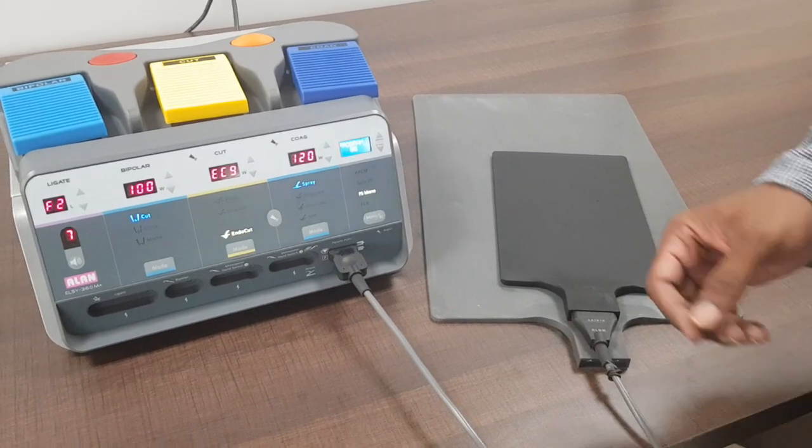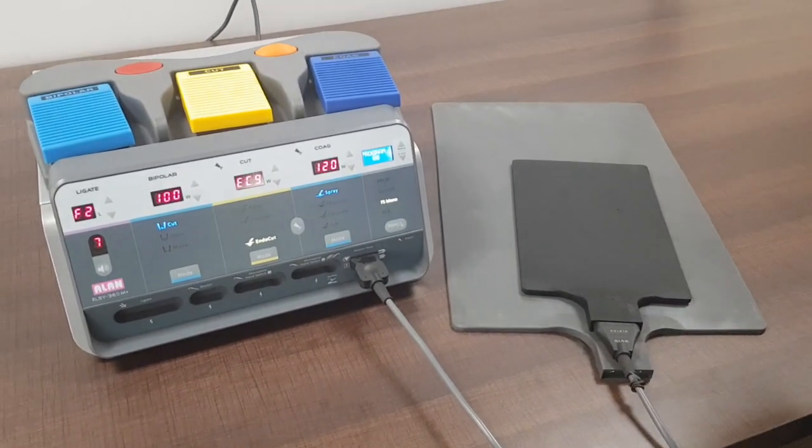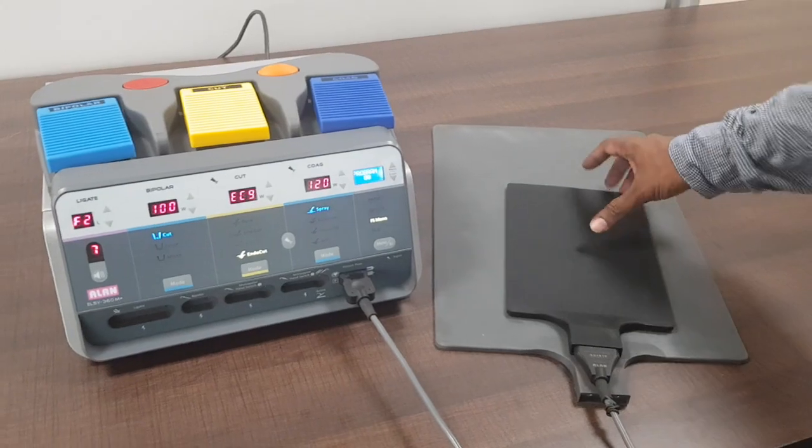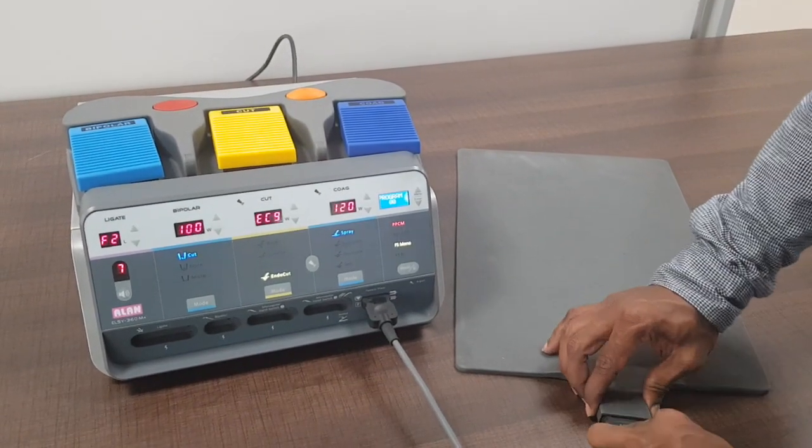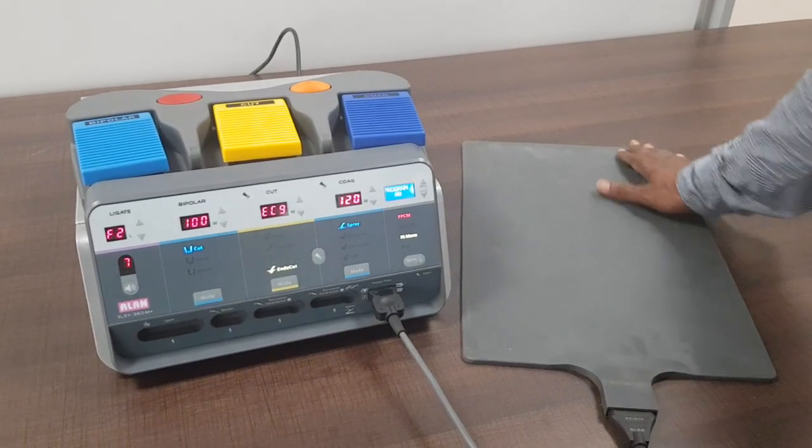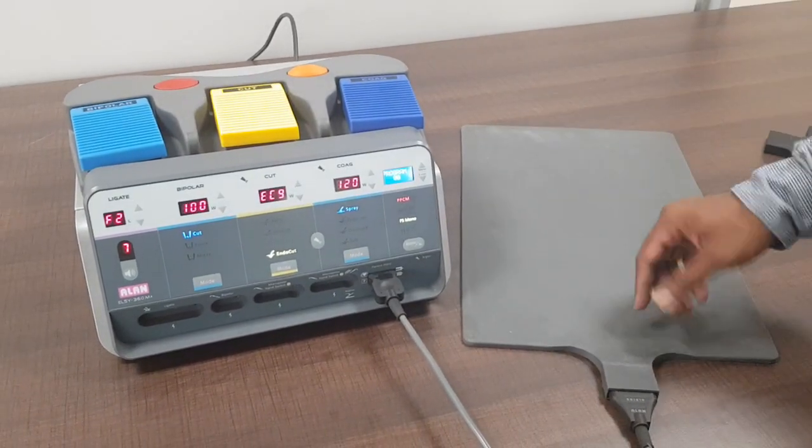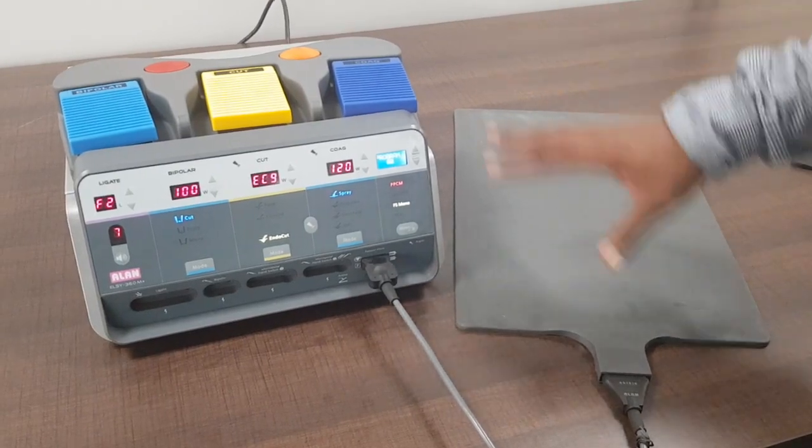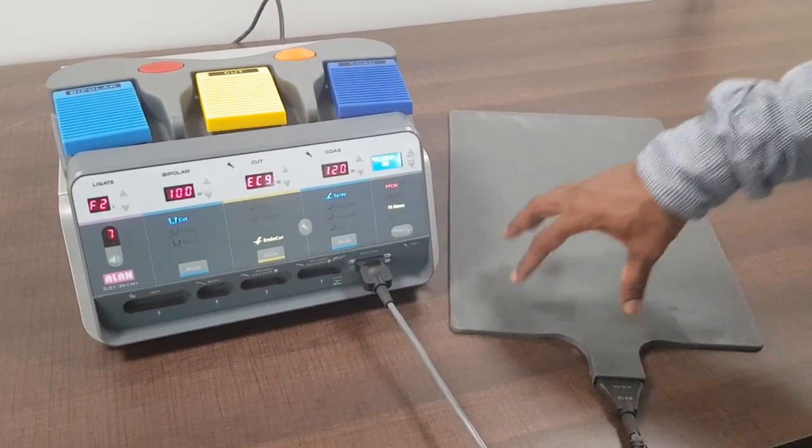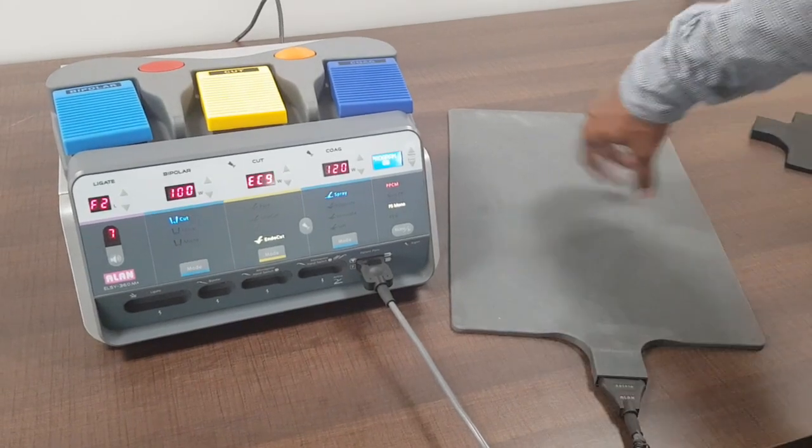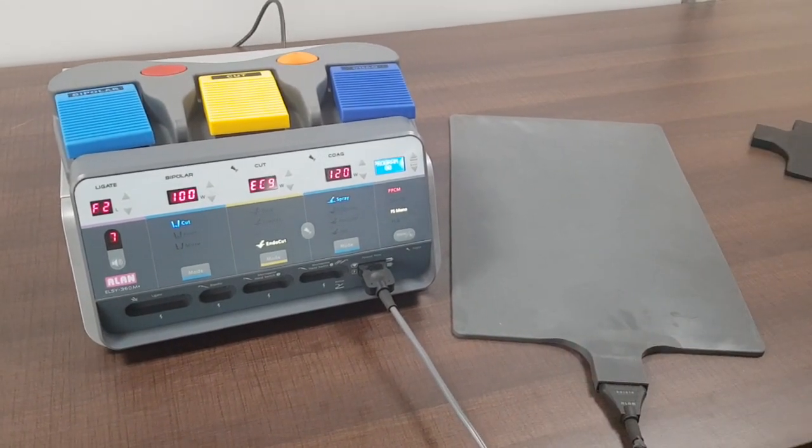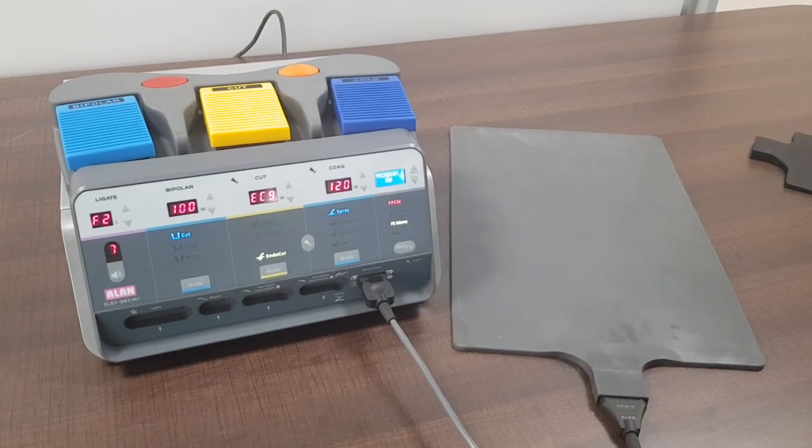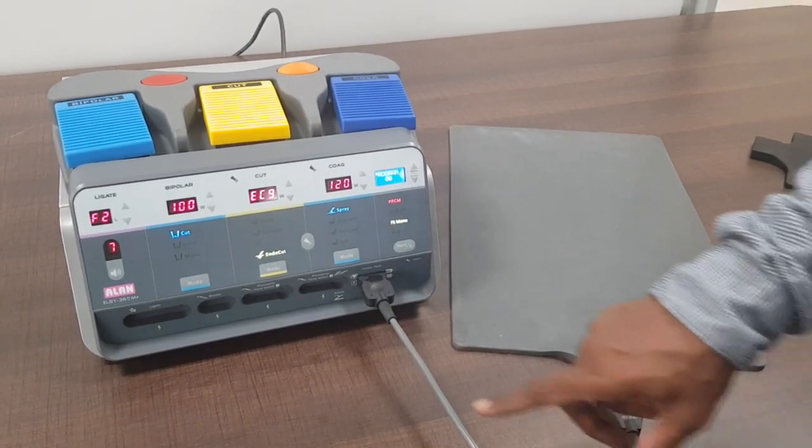But if you see this is another patient plate which is very bigger in size and much more efficient. If we compare these both, in this kind of patient plate you have to use gels so that there is a body contact and it's safer so that there is no alternate side burn or skin burn. But when we connect in this here you don't have to apply any kind of gel. It uses air as the medium and a patient can sleep on this directly and we can operate. We are working on this one and pretty soon we are going to, this is a prototype, we are going to come up with something better and I'll share those videos with you.